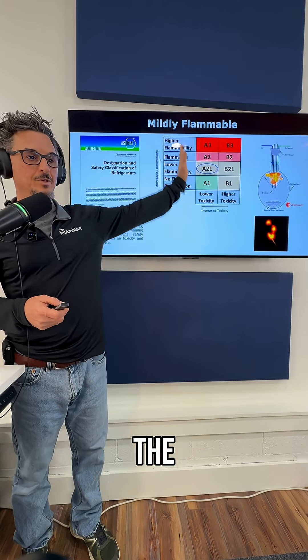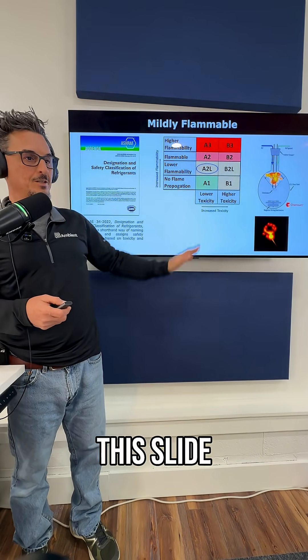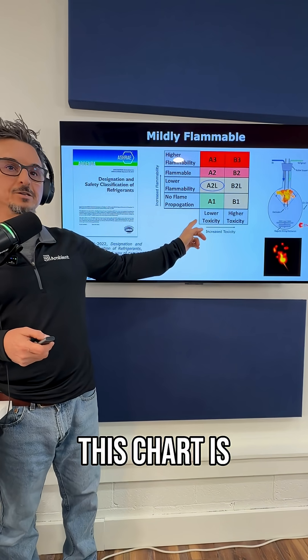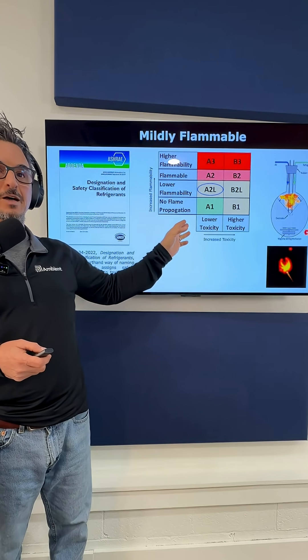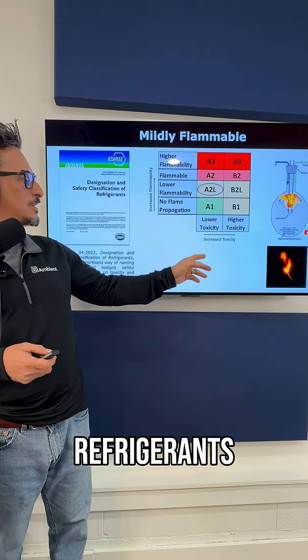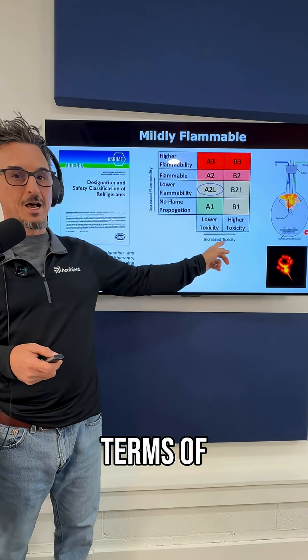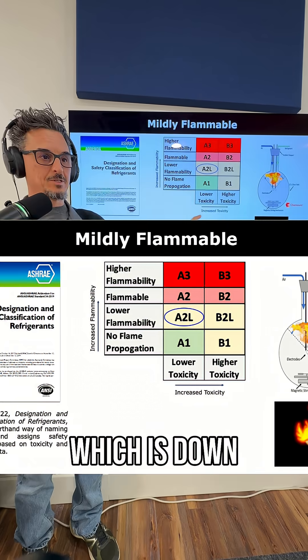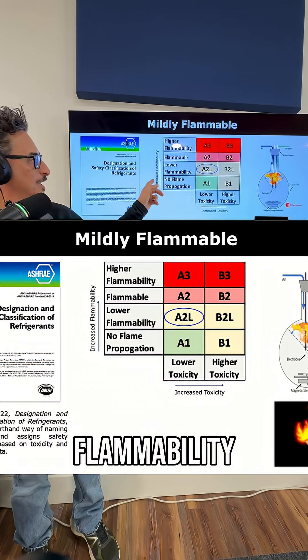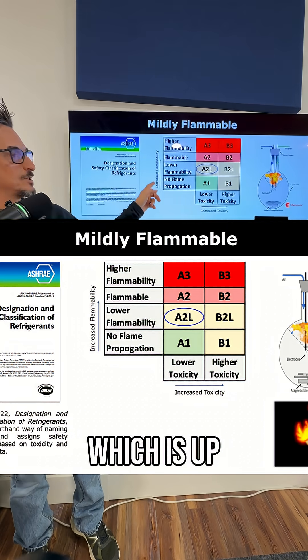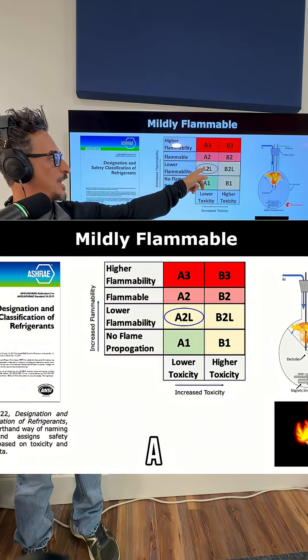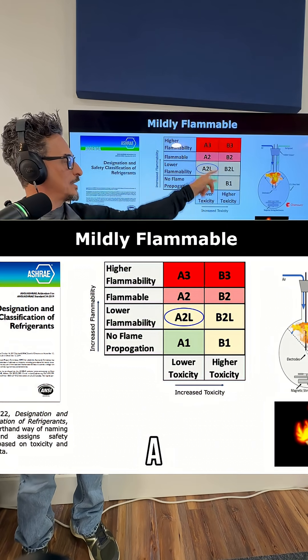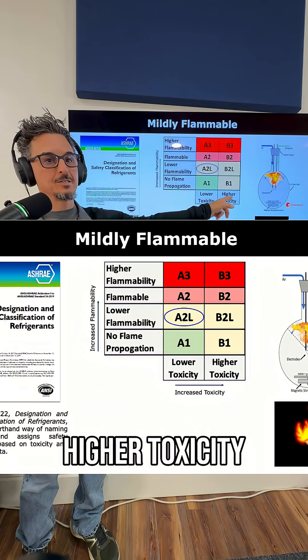Moving on to the middle part of this slide, this chart is directly from ASHRAE 34. It classifies refrigerants in terms of toxicity, which is down here, and flammability, which is up here. Lower toxicity is designated A, and higher toxicity is designated B.